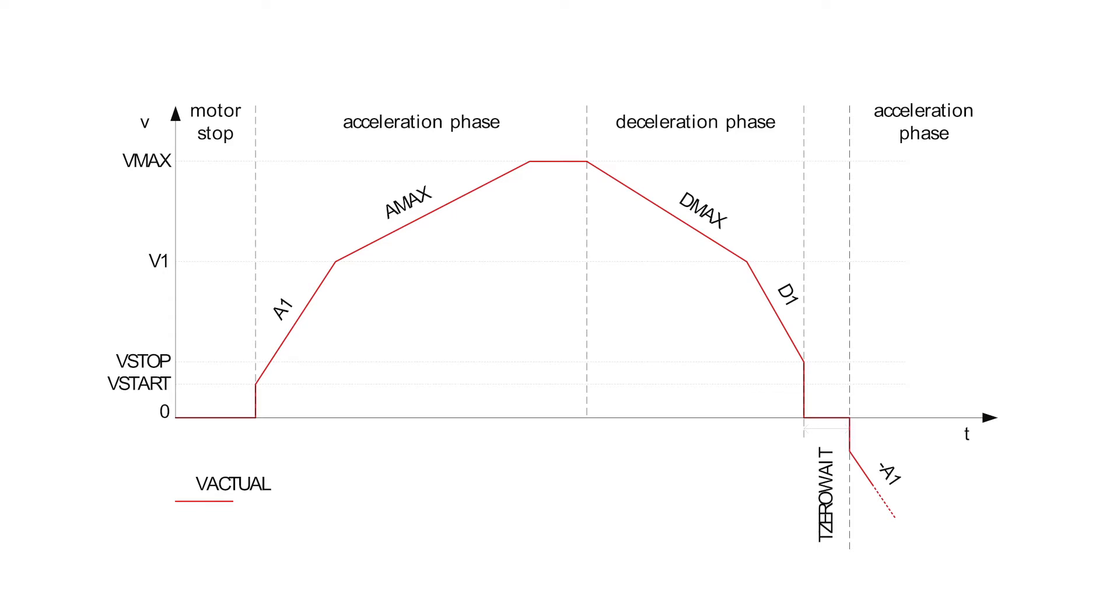The next level is the six-point ramp. What's the difference? We know from a certain point, the torque reserve of the motor decreases with velocity. We can use this fact to accelerate very fast from the standstill and decrease the acceleration at a certain velocity to ensure enough torque reserve. This behavior can be the same for the deceleration phase.